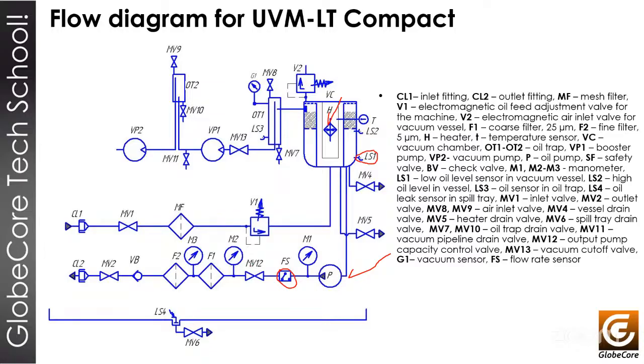We have the MV12 valve to close the flow rate into the filters of fine particles, and then we have the out stage of the machine. And we have here another sensor, LS4, which detects if we have leakage in the machine. If we have leakage and the oil level in the tray increases, that means the LS4 will be activated and will disconnect the machine for its revision, and you will review if you have problems in some part of the machine, and if you have to solve the leakage.